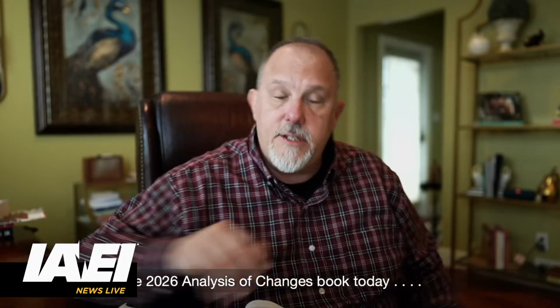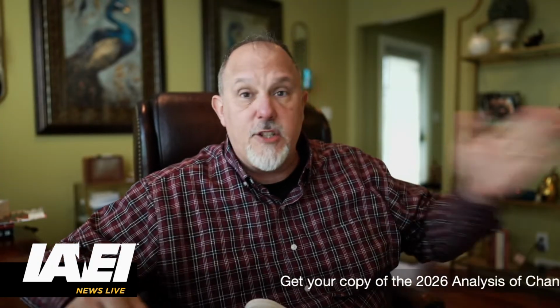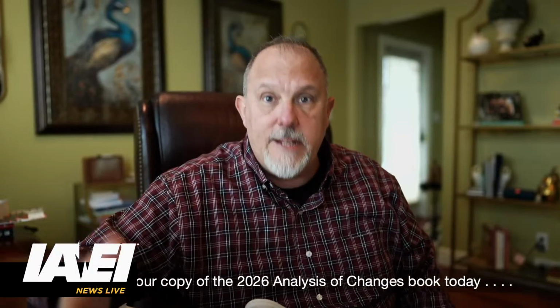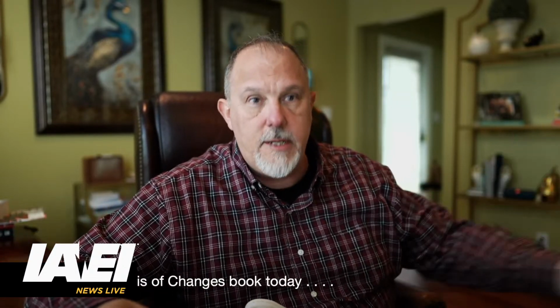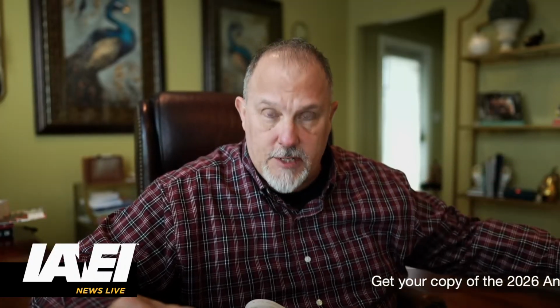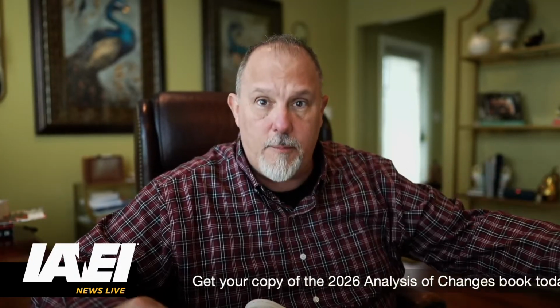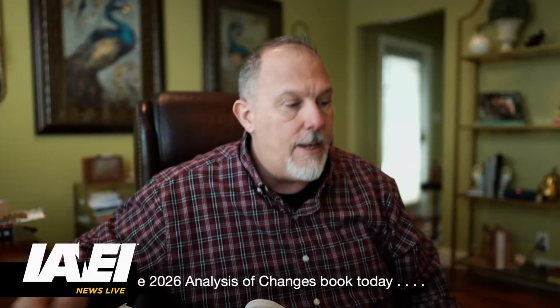The other school of thought is the 210 people saying, no, we want this in here because we're using appliances to identify the branch circuit. It's not an appliance requirement, it's a branch circuit requirement, just like we use the receptacle to identify which branch circuit needs GFCI protection without it being a receptacle requirement that gets moved to 406.